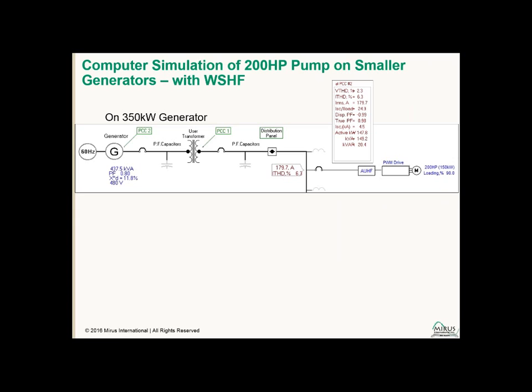So then we decided to do a simulation on a smaller generator with the passive filter solution. Now the customer wanted to reduce the size of the generator. They didn't want to go too small because they were nervous about all the problems they had initially with the smaller generator. So we simulated at 350 kilowatts.